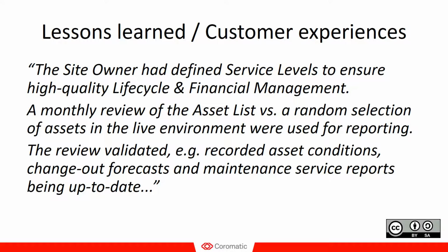So in this case, there was a monthly review of the asset list versus a random selection of assets in the live environment. It was basically selecting a random number of assets and then validating their condition, their change-out forecasts, and the maintenance service reports, that they were up to date compared to the planned maintenance for them or the corrective maintenance that had been performed.